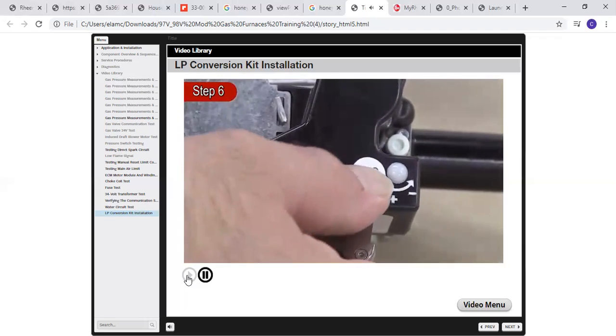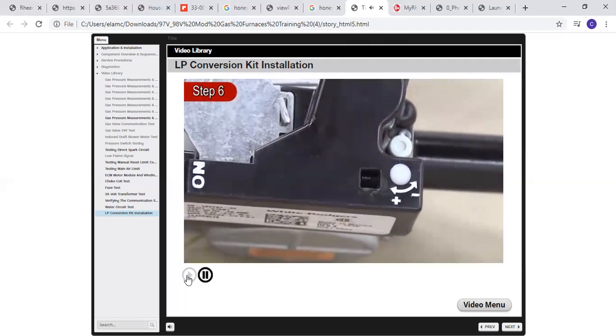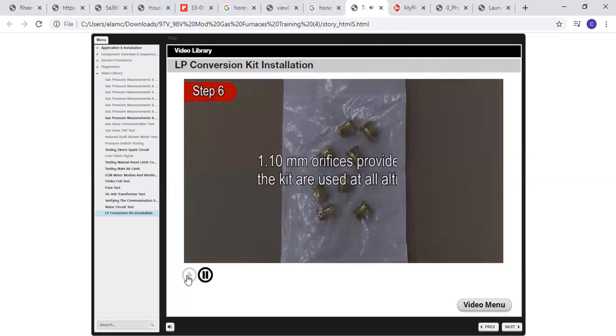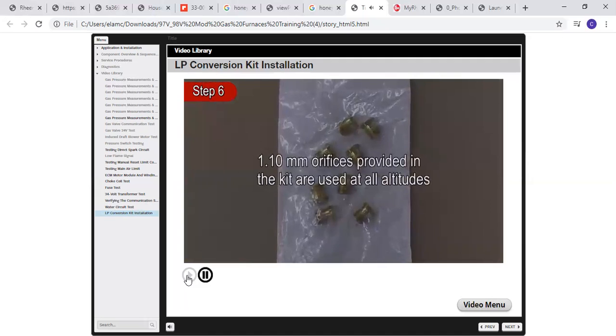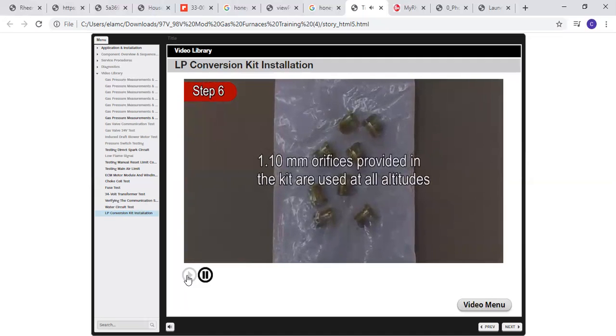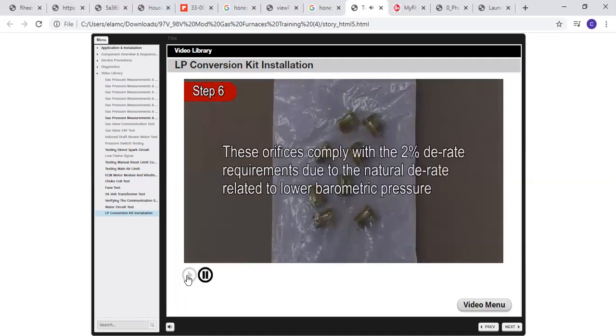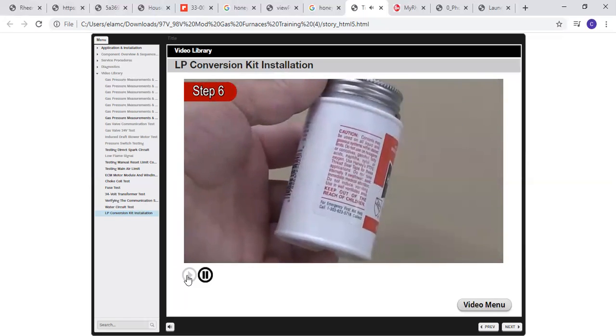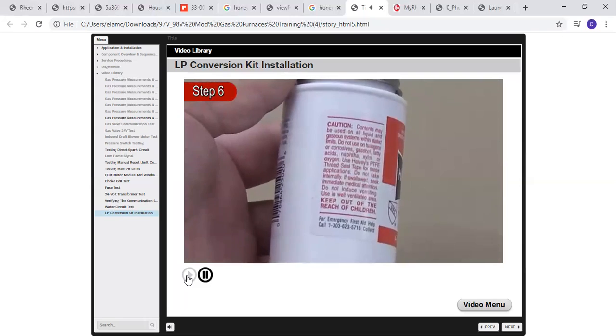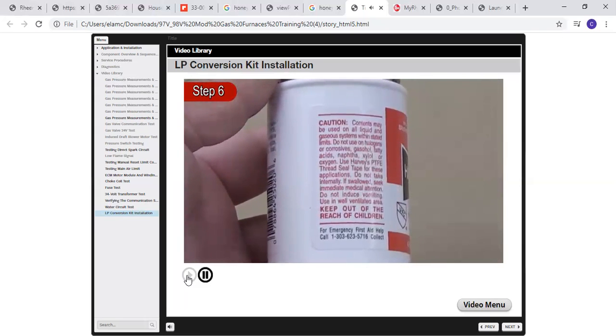To convert to LP, the label over the jumper well will need to be removed. Note, 1.10 millimeter orifices provided in the kit are used at all altitudes. These orifices comply with the 2% derate requirements due to the natural derate related to lower barometric pressure. Note, use a pipe compound resistant to the action of liquefied petroleum gases in all threaded pipe connections.